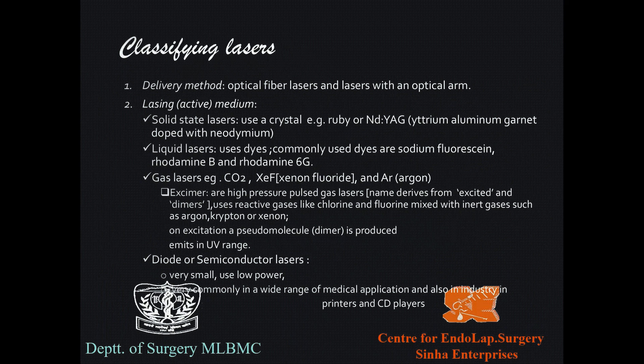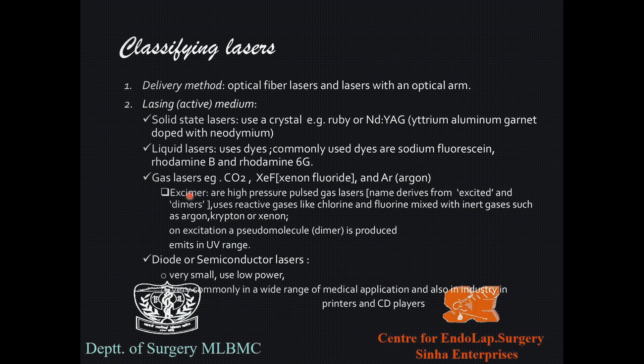Lasers are classified in several ways. By delivery method: optical fiber lasers versus those delivered through an optical arm. By lasing medium: solid state lasers using a crystal — most commonly ruby or Nd:YAG (neodymium yttrium aluminium garnet); liquid lasers using dyes; and gas lasers, most commonly the carbon dioxide laser, also xenon fluoride and argon lasers.